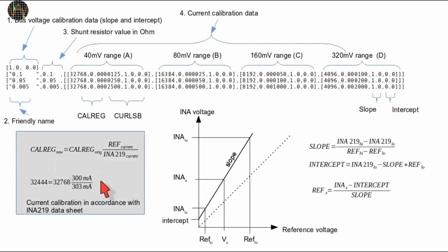For example, if we apply 300 milliamps, but the INA219 reads 303 milliamps, then you calculate the scale factor and end up with a new calreg of 32,444 instead of the original 32,768. Of course, you have to do this separately for each current range.